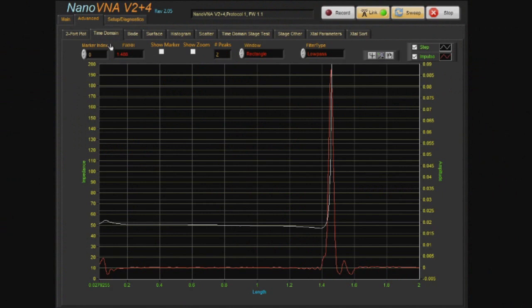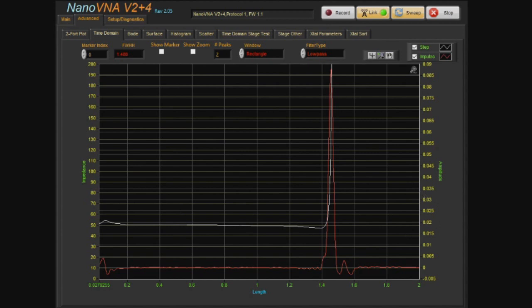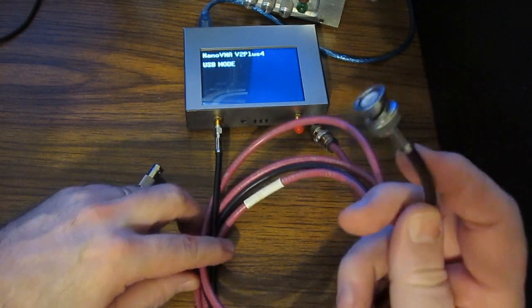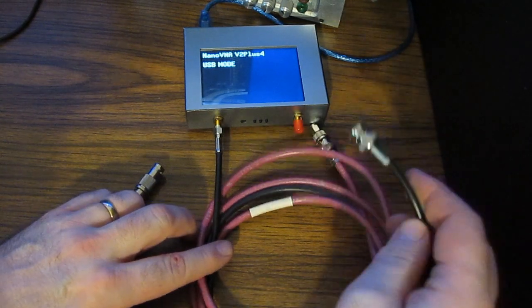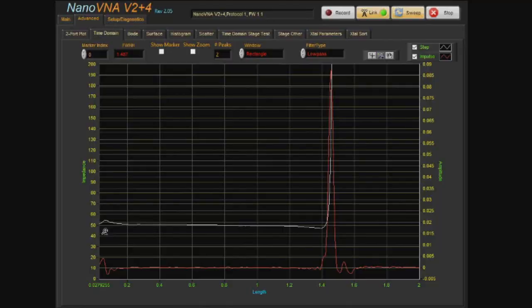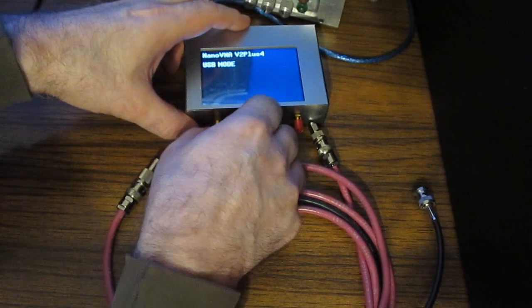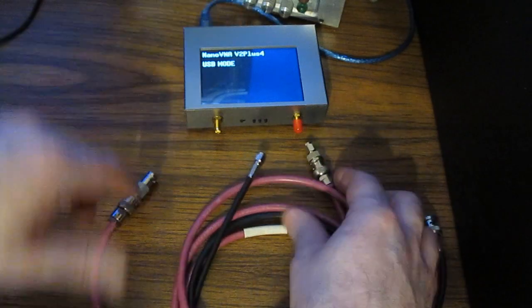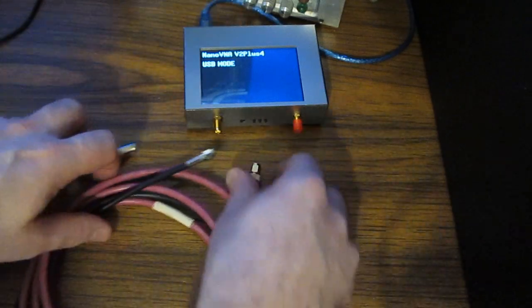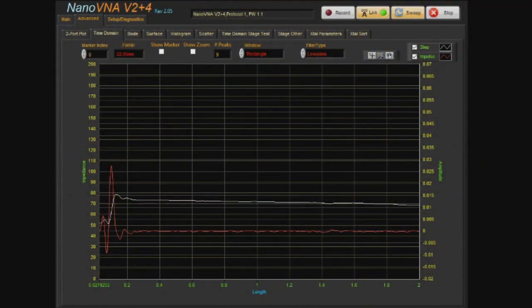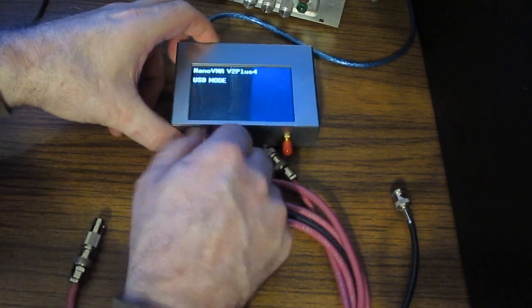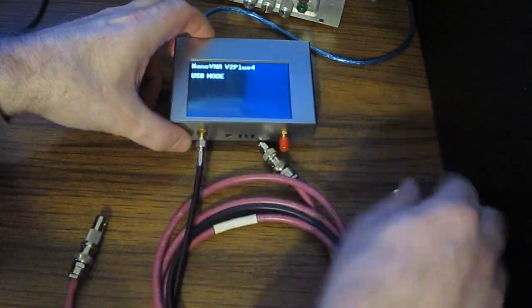For this last demonstration, I have a couple of pieces of coax. Let's attach our first piece of coax and switch over to TDR mode, going to advanced time domain. One of the things you may notice is there are now two scales. The left one is looking at the step impedance and the right scales for the impulse. We can see right now we have a 50 ohm cable attached and there's nothing terminated on the back side, so it just goes off into infinite. Let's try connecting our pink cable and you can see this is a 75 ohm cable.